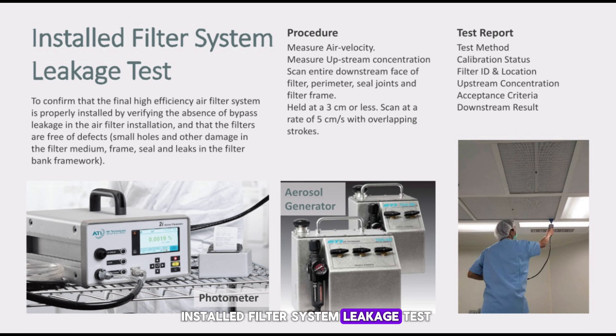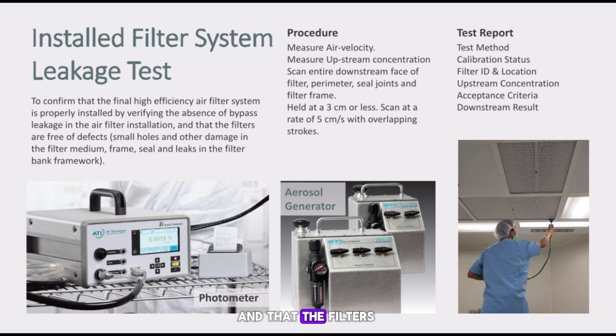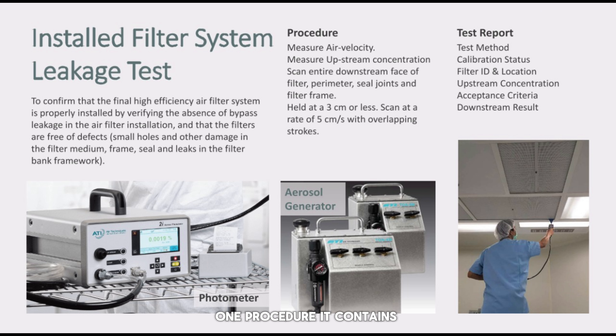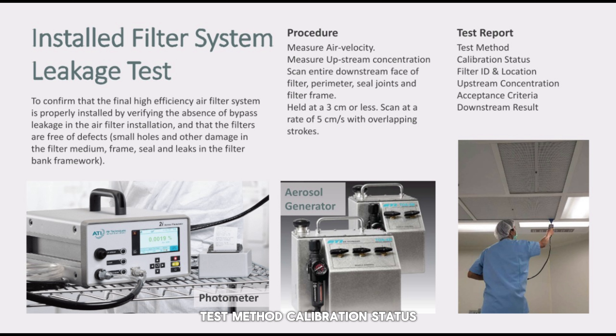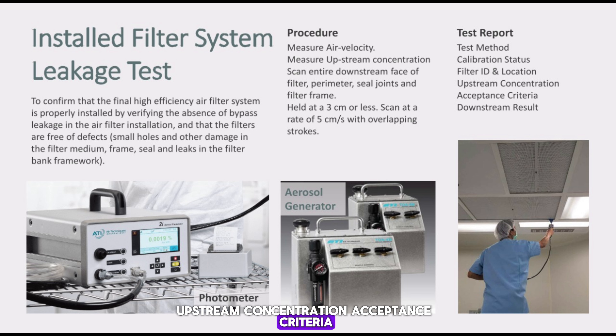Installed Filter System Leakage Test — Purpose: to confirm that the final high-efficiency air filter system is properly installed by verifying the absence of bypass leakage in the air filter installation, and that filters are free of defects like small holes and damage in the filter medium, frame, seal, and filter bank framework. Procedure: measure air velocity, measure upstream concentration, scan the entire downstream face of filter including perimeter, seal joints, and filter frame, held at 3 cm or less, scanning at a rate of 5 cm per second with overlapping strokes. Test report contains: test method, calibration status, filter ID and location, upstream concentration, acceptance criteria, and downstream result.